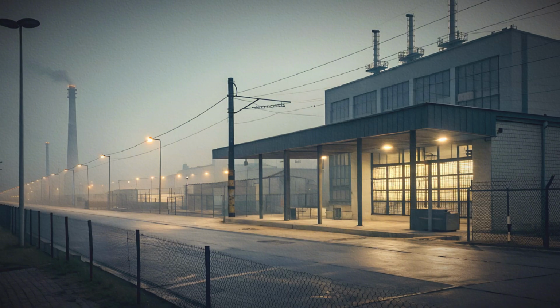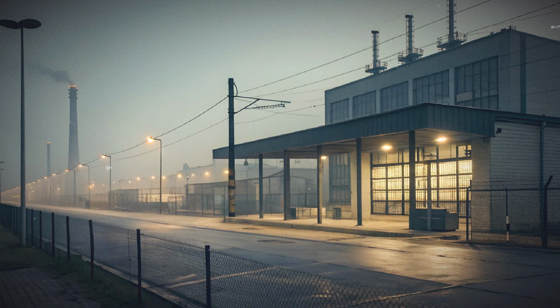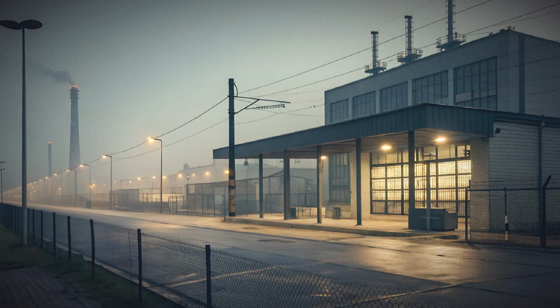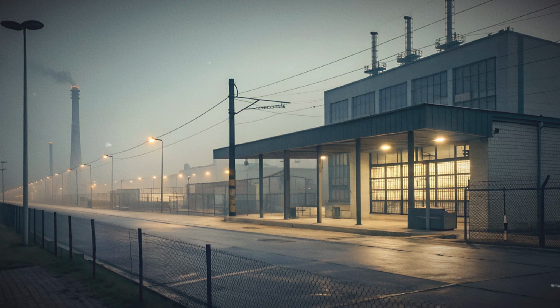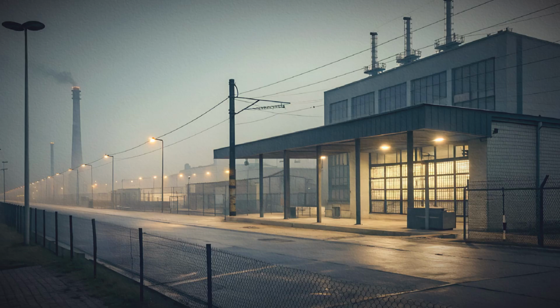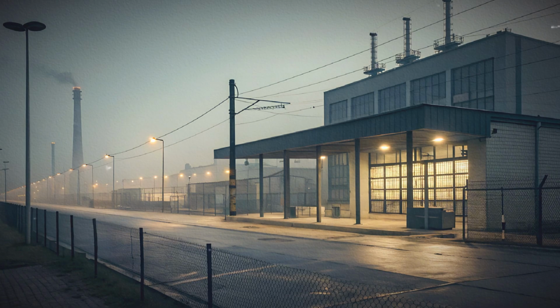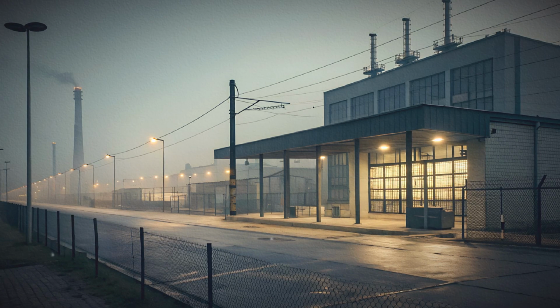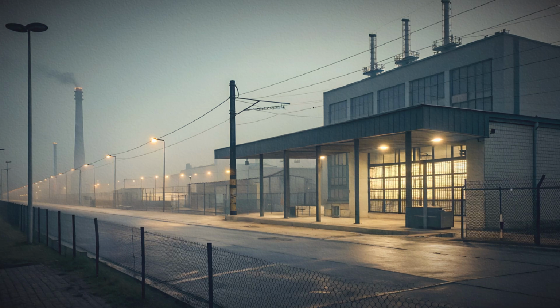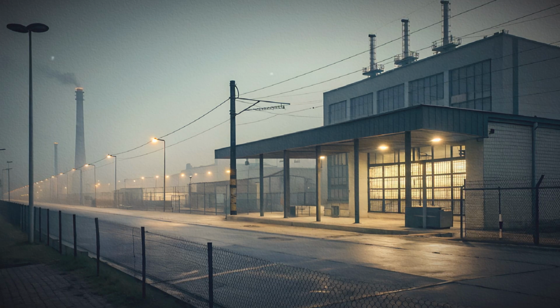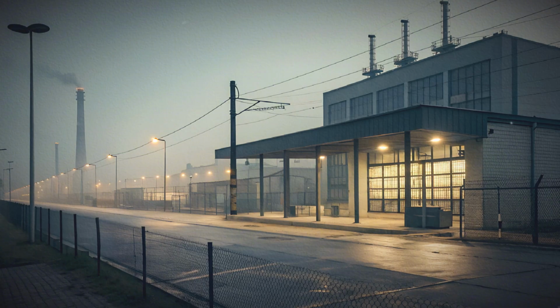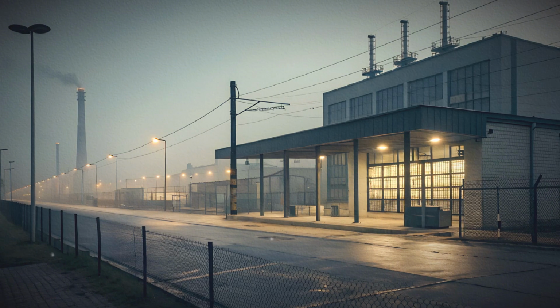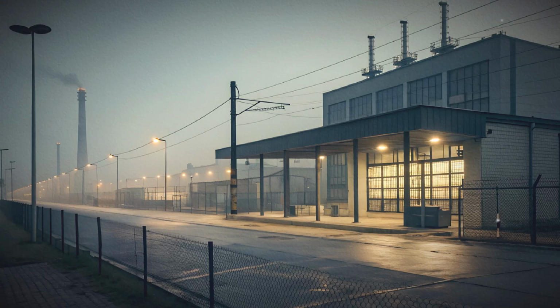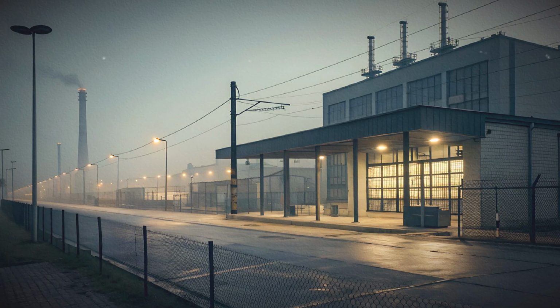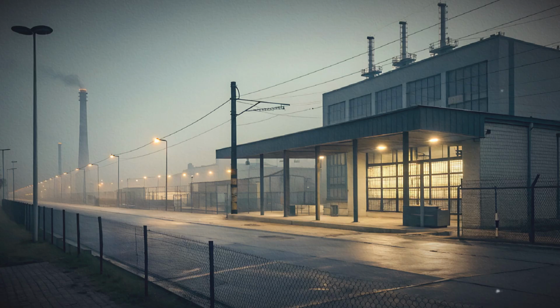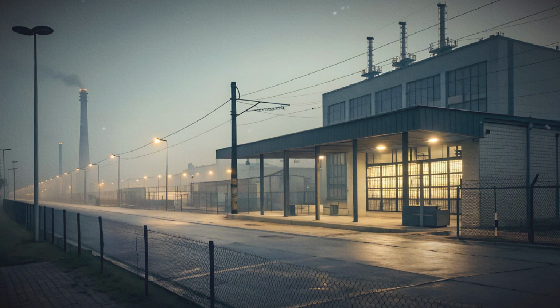Maintenance planning operates on a weekly to monthly rhythm. Routine inspections are scheduled to align with lower demand periods when feasible. Planned outages for equipment replacement or major testing are coordinated across regions to avoid concentrated impacts. Work orders are prepared in advance. Teams follow established procedures for isolation, testing, and restoration. Coordination involves operators, field crews, planners, and contractors. Documentation tracks each task and its completion.